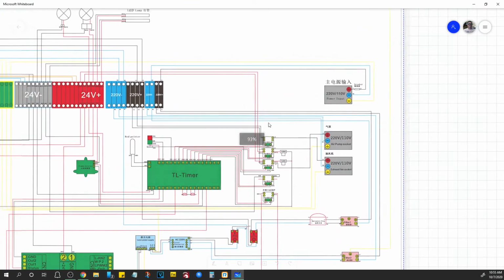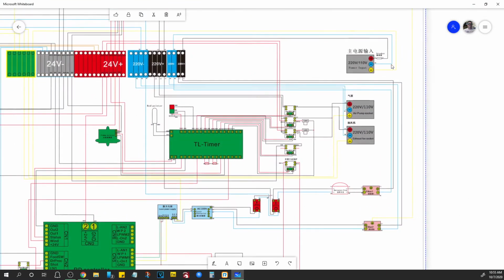Now this is your AC power block. This is where your main power input is. This is where that quarter turn quick lock connector goes. And there's a circuit breaker you'll notice here, not a fuse anymore. Since about 2019 there's been circuit breakers there. Now they're not in the right spot here. They just renamed that from fuse to breaker. The breaker is actually on that main power termination rail that's in the electronics bay, but you'll see it.